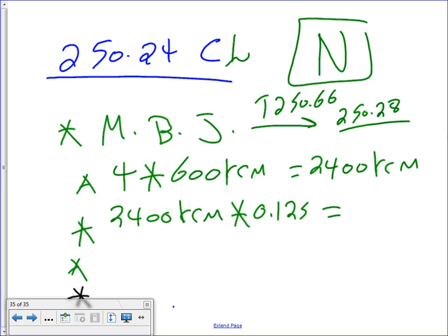I didn't do the math on that one. 0.125 times 2400, yep, equals 300. Equals 300 kcmil. Okay, 300 kcmil. That's the size of the main bonding jumper.